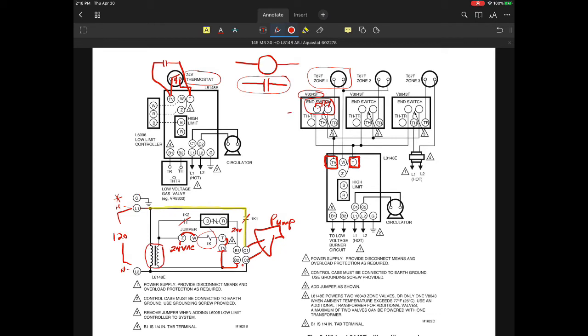So on any type of zoning system, if we ever had a question, like, gee whiz, I don't know if my thermostat called this zone valve open, the first thing you'd really want to be checking is: is the zone valve actually energized, and is it actually opening? Usually a lot of our residential zone valves can be normally closed or normally open, but most of them are going to be normally closed, and you power them to open them up.